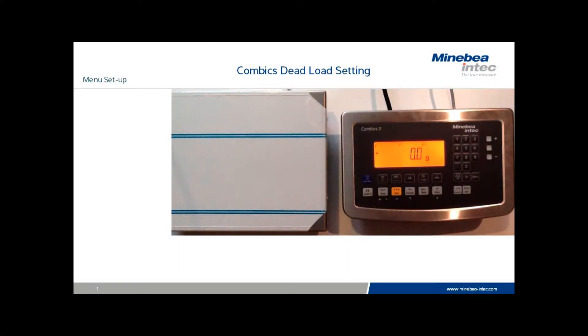This video outlines the procedure for setting dead load values to deduct the weight of fixtures and permanent tare vessels. Minebea terminology is somewhat different from other instrumentation. In the Combics menu, you will see the word preload when describing the function more commonly known as dead load, but both terms are identical in function.